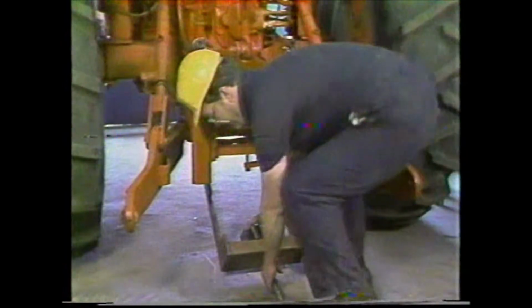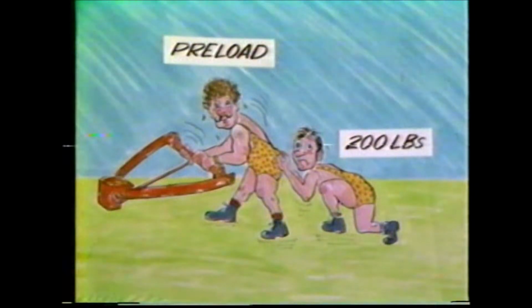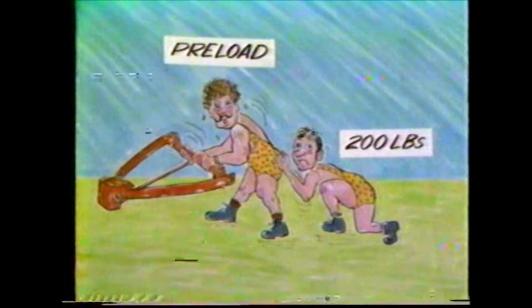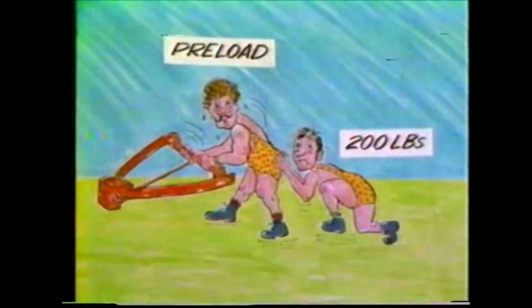The next step is to check the pounds of pull required to operate the Draft-o-Matic system. A general rule of thumb to follow is that it takes approximately 200 pounds of pull greater than draft spring preload to activate the Draft-o-Matic system.